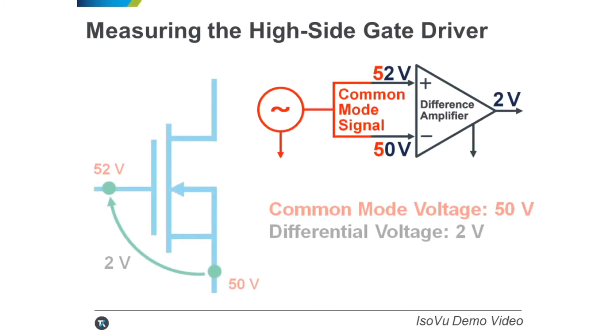Remembering our previous example of measuring 2 volts differential in the presence of a 50 volt common mode voltage, this measurement can only be made using a probe with high bandwidth, high common mode voltage range, and high common mode rejection. A higher CMRR will reject more of the signal common to both test points.